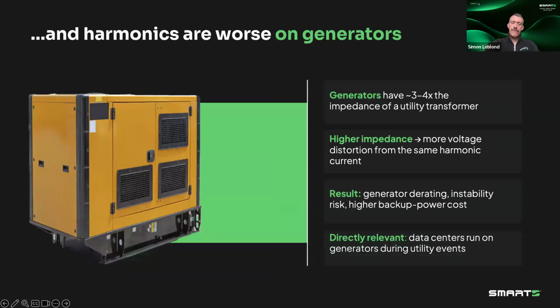And then, I mentioned it before, the generators. There's another impact because they have roughly 3 to 4 times the source impedance of a utility transformer. And so that higher impedance means there's more voltage distortion from the same harmonic current, Ohm's law. I promised no equations, so I'm just going to mention Ohm's law. But basically, at that point, with that generator, you generally need to derate it, and you have an instability risk when you go on backup power. And this rule will also apply to UPS systems, which also have this elevated impedance. I'll talk about what the cycle is there in a moment.